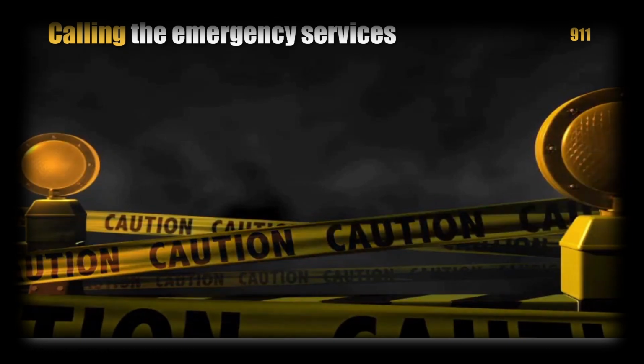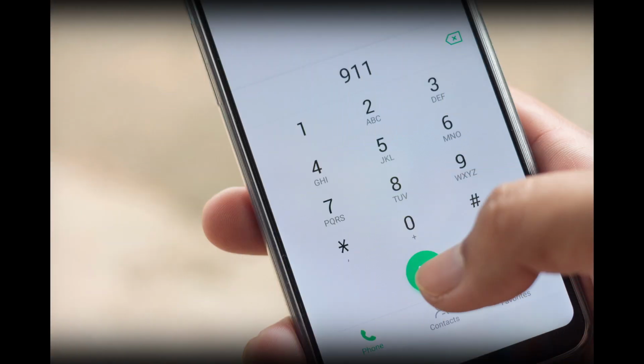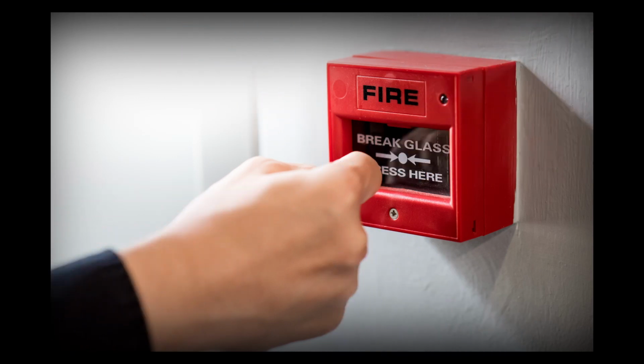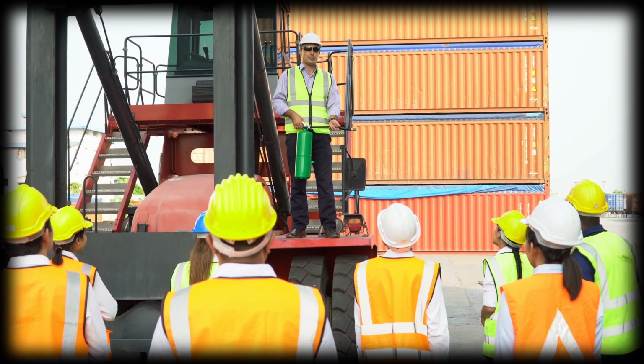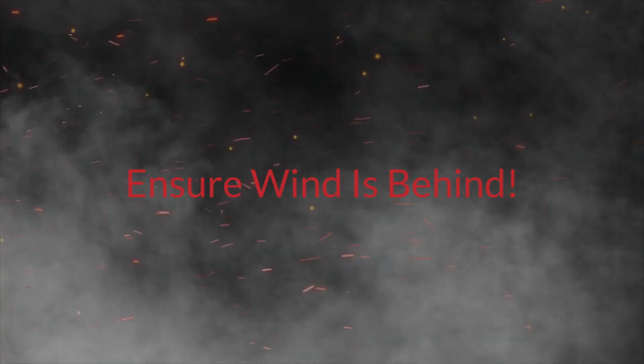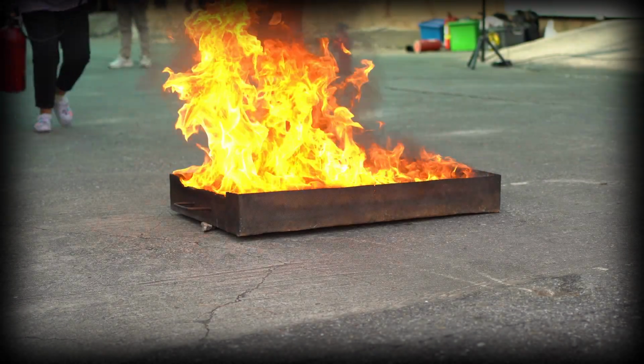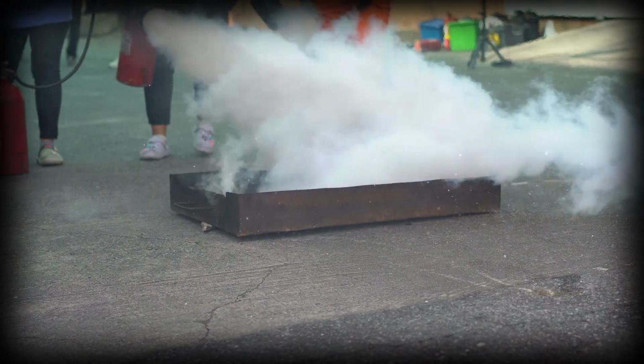If you find a fire at work and decide to use a fire extinguisher, ensure the fire department is alerted or the alarm is activated, ensure the building is being evacuated, confirm the fire is small and contained, identify the fire's source, ensure a safe exit is behind you, have the appropriate extinguisher at hand, be confident and trained in the extinguisher's use. If you're in a windy area or where there's a clear airflow direction, ensure the wind is behind you to prevent the fire extinguisher contents from blowing towards you. Stand approximately 8 to 10 feet away from the fire and apply the PASS method to put it out.